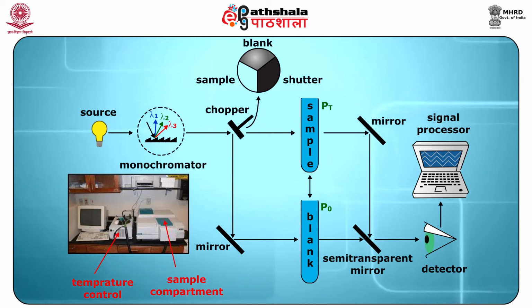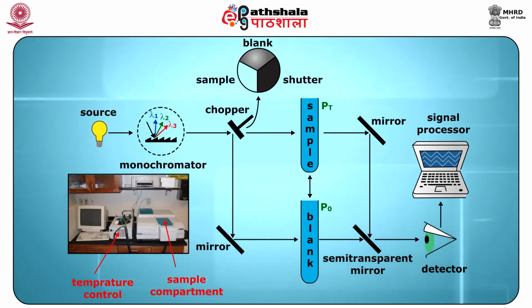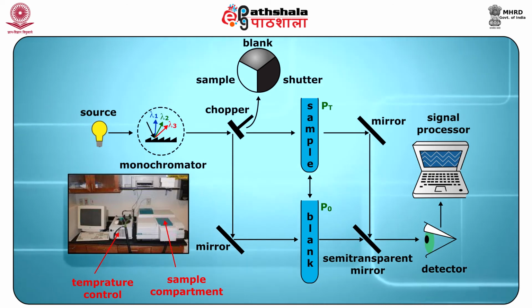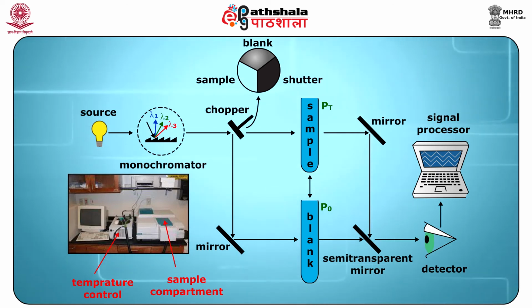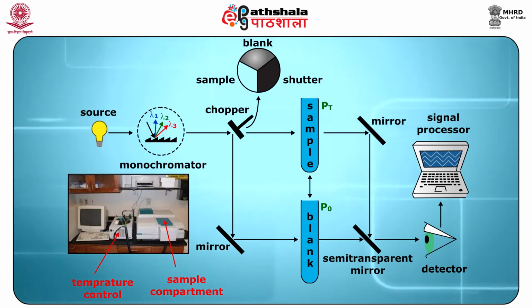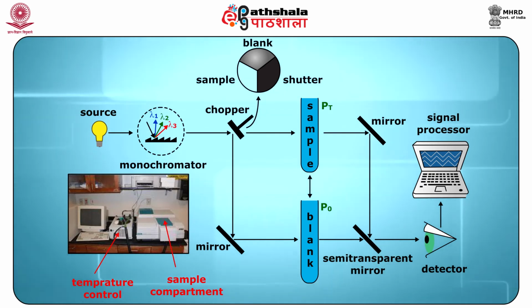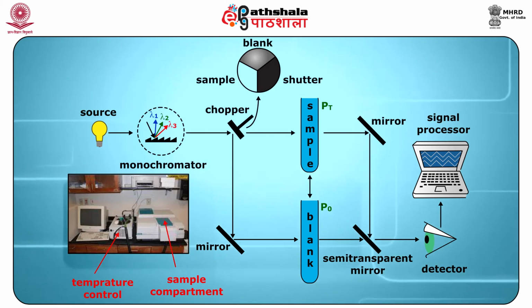It is possible to continuously adjust it to 0% transmittance by including an opaque surface as a shutter. By adjusting the monochromator's entrance and exit slits, the effective bandwidth of a double beam spectrophotometer is controlled. Values for the effective bandwidths are commonly around 0.2 to 3.0 nanometers.